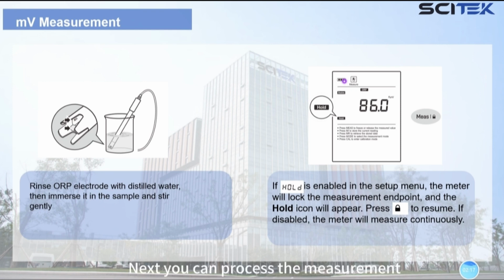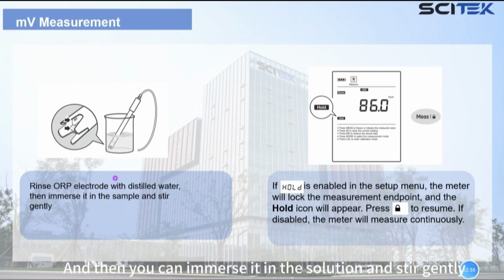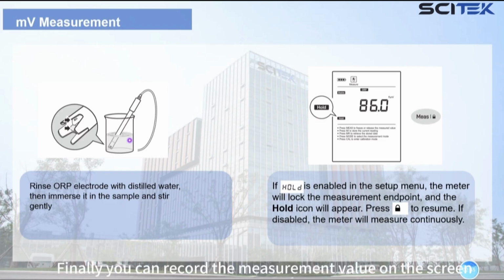Next, you can process the measurement. First, we press the mode button until the ORP shows. Then you can rinse the ORP electrode with distilled water. And then you can immerse it in the solution and stir gently. Wait for the measurement to stabilize. Finally, you can record the measurement value on the screen.